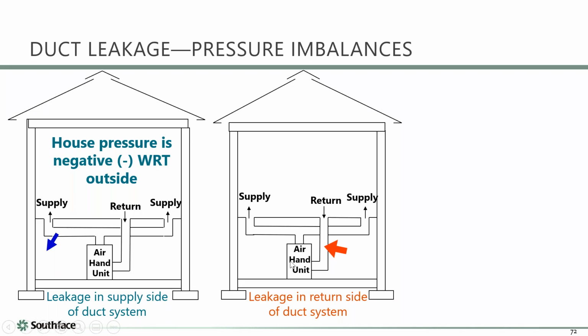And over here, all the supply air, all 1,000, goes into the house, but you're only taking out, say, 700 because of 300 CFM of leak on the return. That house is going to go positive. You can do this test. I bet people on this call, I know some of them have blower doors. If you have an accurate pressure gauge, you can just run a tube outdoors.